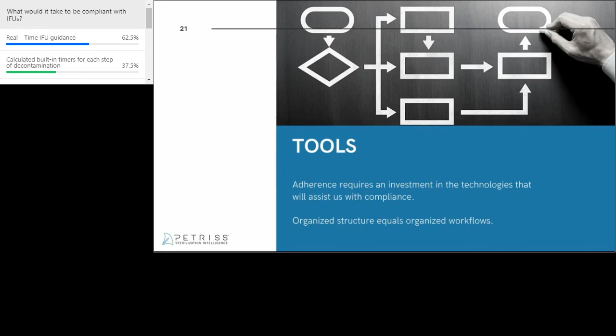And the final piece here comes down to tools. This is something that we haven't spent a lot of time on in this presentation, but it's a critical part of true IFU compliance. I mentioned it a little bit earlier when I said that IFUs are not constrained to sterilization parameters, particularly when you're talking about things in the inspection stage, like a visual inspection inside cannulated instruments, for instance, or some type of lighted magnification on the tip of an endoscope, the things that AAMI ST91, for instance, says that you should be doing.